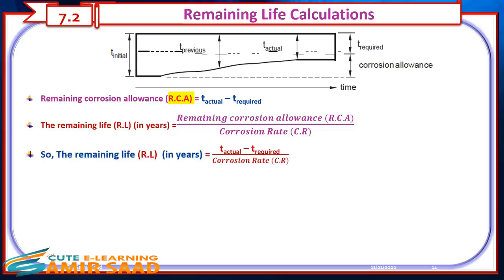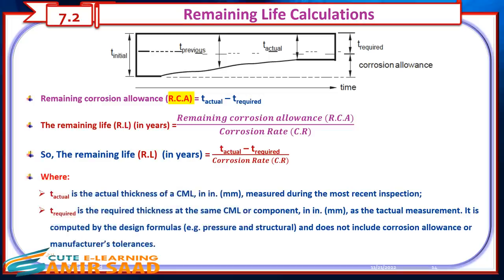Remaining life, in years, equals T-actual minus T-required, divided by the corrosion rate. Where T-actual is the actual thickness of a CML measured during the most recent inspection, and T-required is the required thickness at the same CML or component — computed by design formulas such as pressure and structural requirements — and does not include corrosion allowance or manufacturer's tolerances.